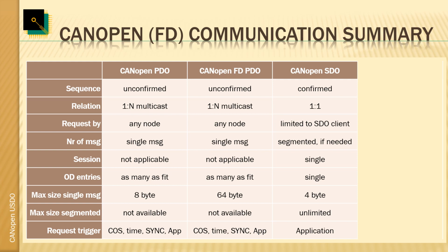And the biggest limitation here is that really the channels available in CANopen are limited. So per default, there's only one SDO client for all nodes. So only one device can be a manager that communicates to all others. With some extra effort we can work around this issue, but the default is that it's only one.